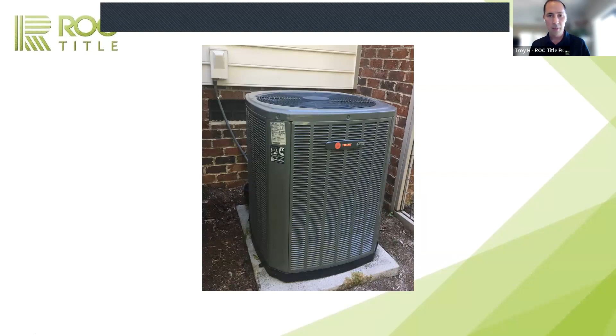What type of refrigerant? Right here, second arrow down: HFC, hydrofluorocarbons, 410A. So this is not R22, this is 410A. Is it a heat pump or air conditioner? Central cooling, air conditioning - so this is not a heat pump, it will not work in the wintertime.